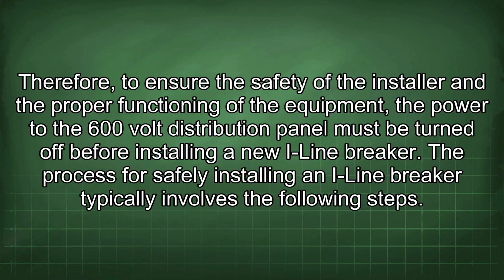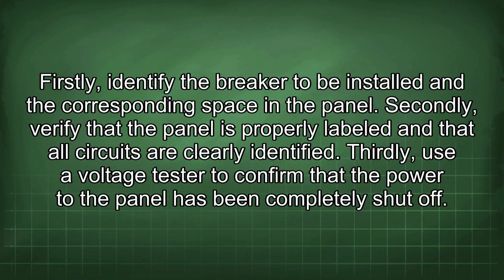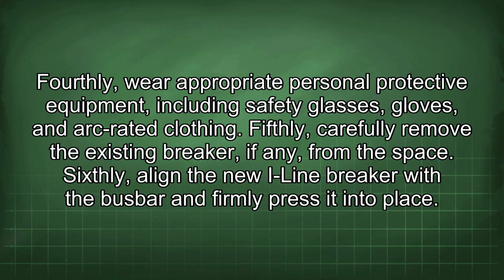Therefore, to ensure the safety of the installer and the proper functioning of the equipment, the power to the 600-volt distribution panel must be turned off before installing a new I-Line breaker. The process for safely installing an I-Line breaker typically involves the following steps. Firstly, identify the breaker to be installed and the corresponding space in the panel. Secondly, verify that the panel is properly labeled and that all circuits are clearly identified. Thirdly, use a voltage tester to confirm that the power to the panel has been completely shut off. Fourthly, wear appropriate personal protective equipment, including safety glasses, gloves, and arc-rated clothing.